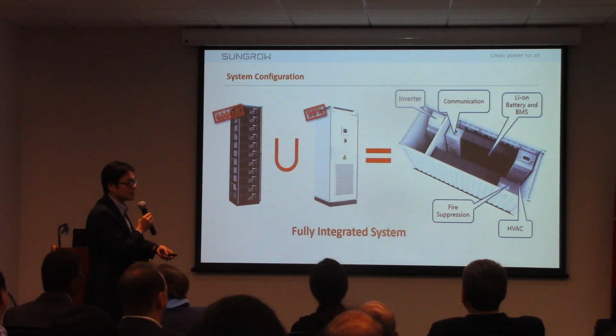As I said, clipping—if you have lots of DC panels with a DC to AC ratio of 1.3, 1.4, using a DC coupled solution, you're well situated to absorb the excess energy into the battery. Then whenever the utility needs backup, or later in the day when there's demand or capacity needed, I can discharge my battery to support it.